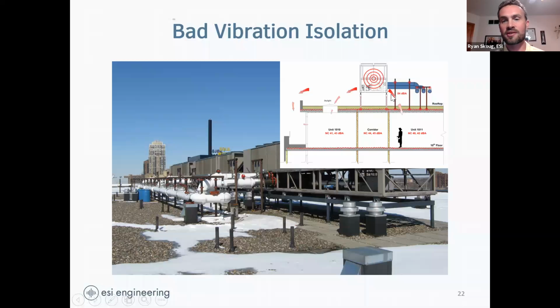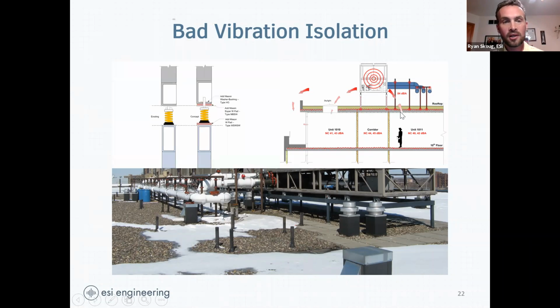So now we're looking at, well, is the noise going through the concrete slab itself of the roof? They've got skylights, is the noise going through the skylight? Is it bending around and going through their balconies? Well, no, it wasn't any of those things. What it was, was just vibration from the structure coming down and vibrating and radiating from all the surfaces, as well as the pipe. The pipe would come off of these units, come down the posts and into the structure and radiate as noise that way.